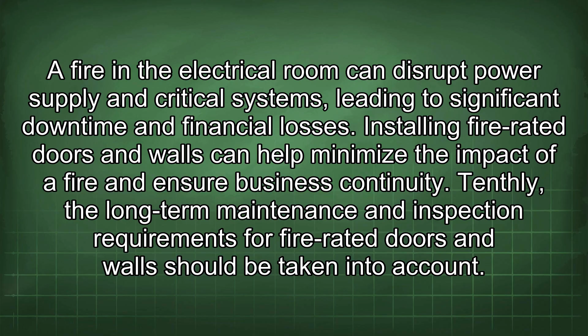Ninthly, the potential impact of a fire in the electrical room on the overall operation of the building should be assessed. A fire in the electrical room can disrupt power supply and critical systems, leading to significant downtime and financial losses. Installing fire-rated doors and walls can help minimize the impact of a fire and ensure business continuity. Tenthly, the long-term maintenance and inspection requirements for fire-rated doors and walls should be taken into account. Fire-rated doors and walls require regular inspection and maintenance to ensure they function properly in the event of a fire. Neglecting maintenance can compromise the effectiveness of these fire protection measures.